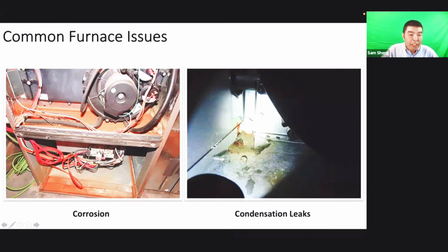For the high efficiency furnace, that's normal. Like this, it's normal. There's rust around, especially around the bottom of the inducer motor. You will see rust corrosion there, because condensate water will collect around the inducer motor, and all the pipe around here, if it's not connected tight, maybe the water comes out too.